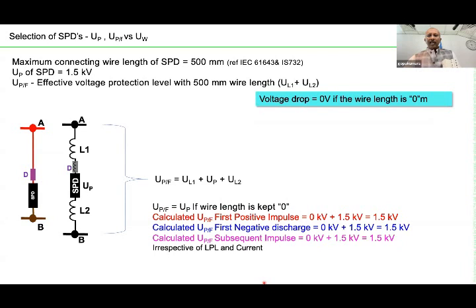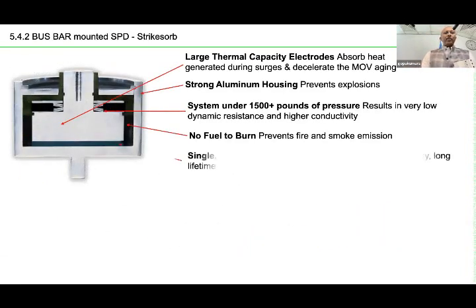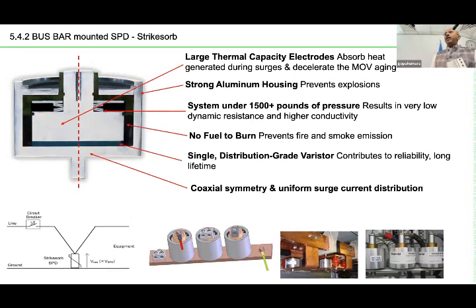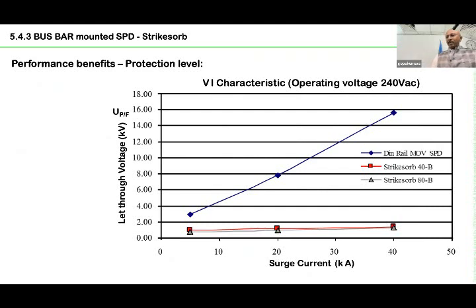Now, what is important in this particular case is the bus bar mounted SPD, which you are directly mounting on the bus bar. As a result, the line length is nil, zero. If you compare the SPDs here, for example, the red line at the bottom is the voltage protection level of a bus bar mounted SPD. This line, which I am moving the cursor along, is the ultimate voltage produced during a transient condition between point A and B. You can see that it is maybe about 1.5 or 1.2 kV.